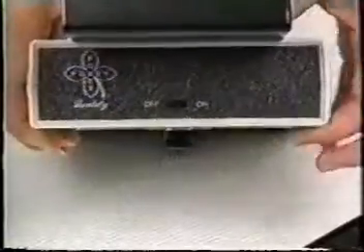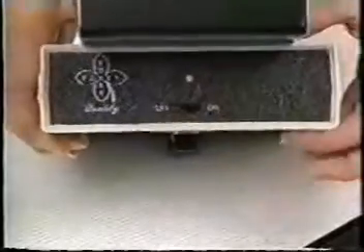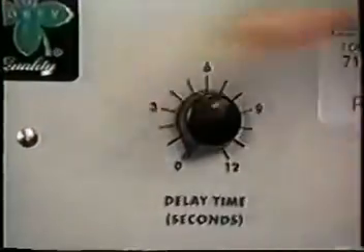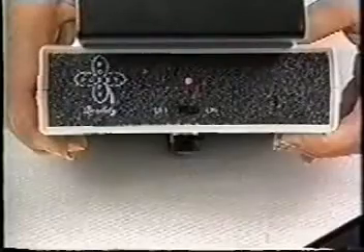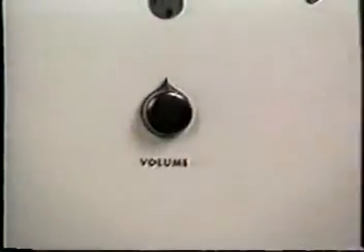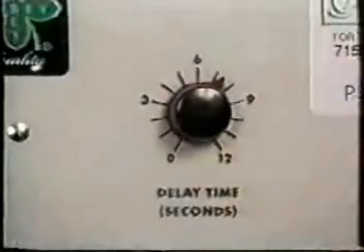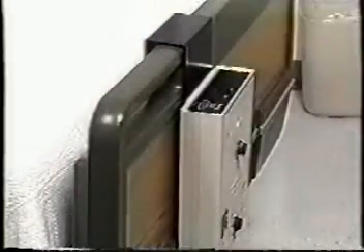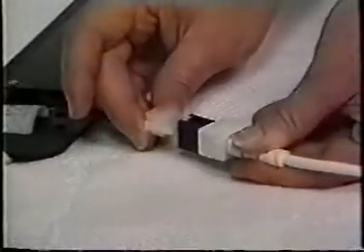Before installing the unit, test it by turning it on and setting the time delay to 0. The device should alarm immediately. Set the volume to the desired level and set time delay to the desired time. Turn off the unit and hang the control unit on the foot of the bed using the bracket. Connect the sensor extension cable to the pad.